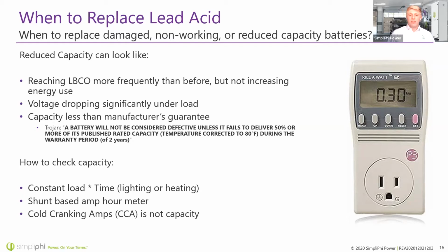However, if you're going to run something like your dishwasher, it's not going to give you a constant load and you're probably not going to know how much power it's even using, so that's not going to be a good thing to use. But let's say you've got a 1,000-watt light bulb, 1,000 watts worth of lighting, and you want to run it for 2 hours. That's 1 kilowatt times 2 hours is 2 kilowatt hours. So that's a great way to check capacity right there. Now, of course, you've got to account for the losses through the wire and the inverter inefficiencies, but those are, I'm going to round to maybe 10% for an average system.